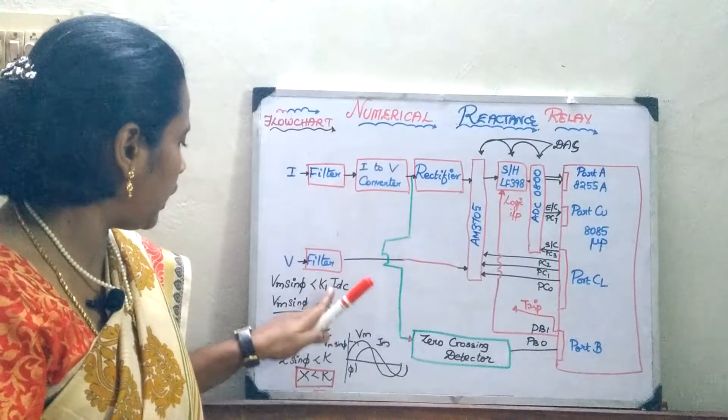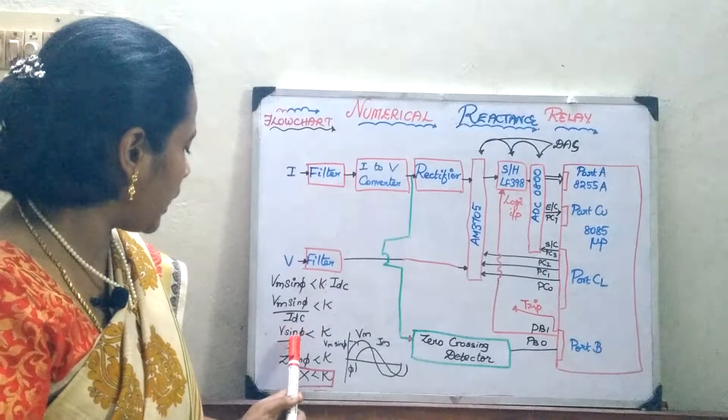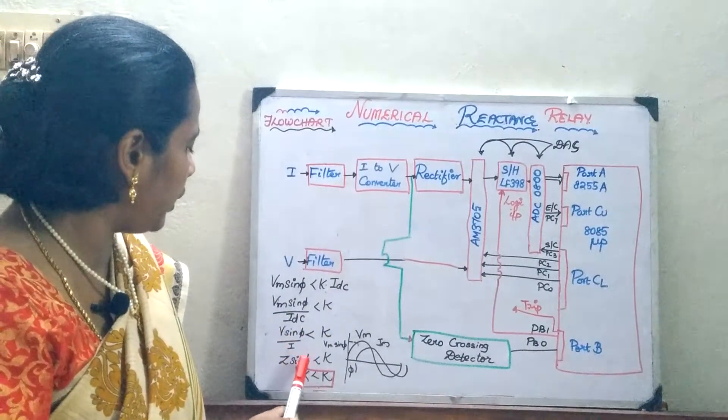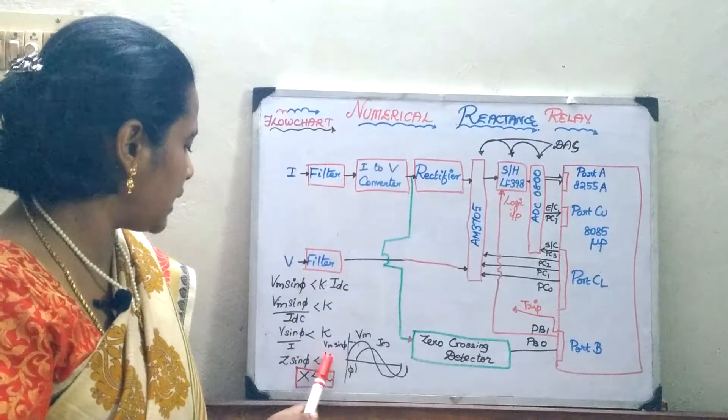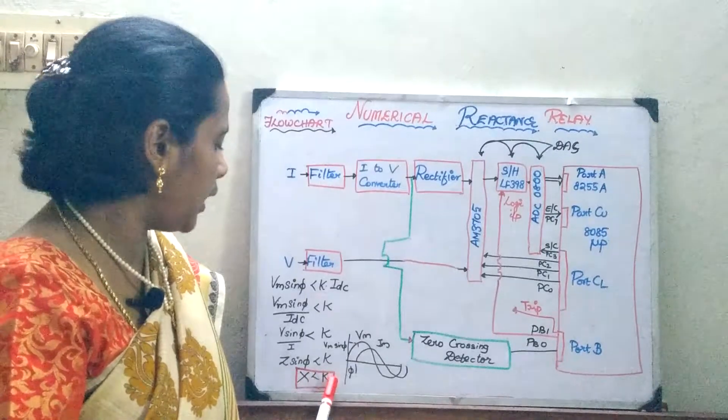Now V into sin phi by I is less than K or else you can say V by I is Z, impedance into sin phi is less than K. So, the sin phi component is nothing but your reactance. If this reactance is going to be less than K, then the relay will operate.